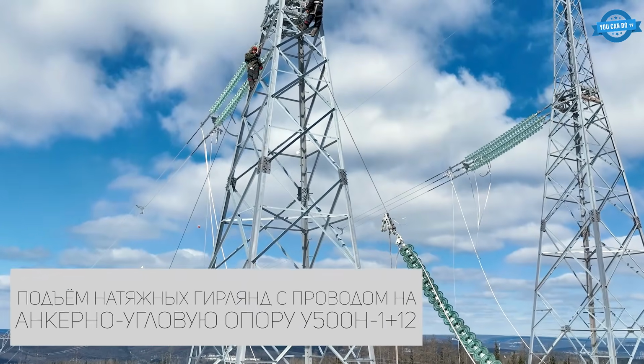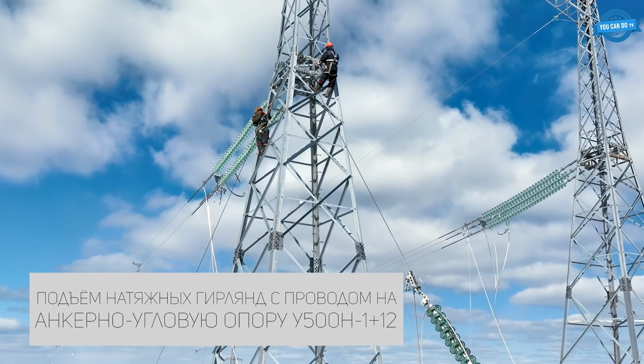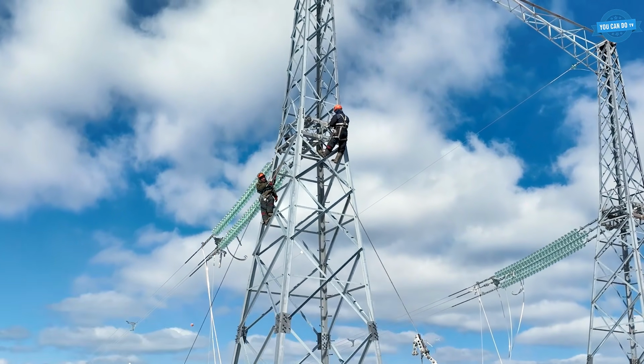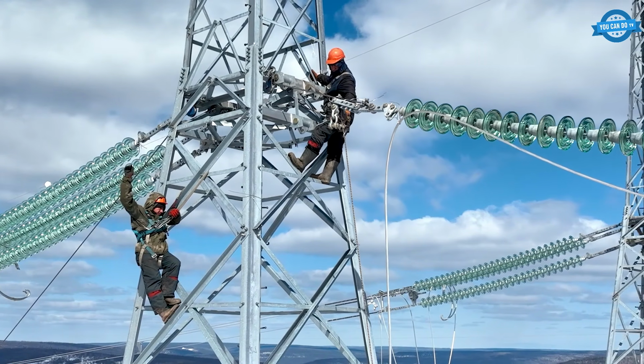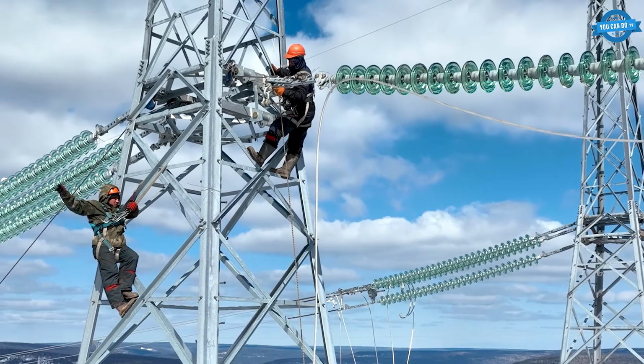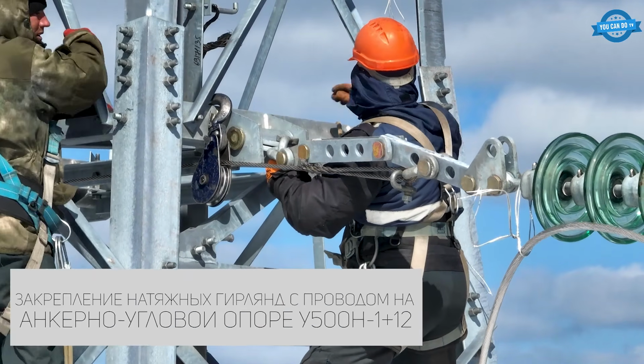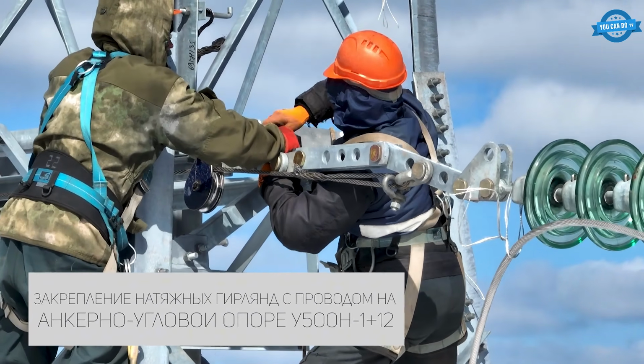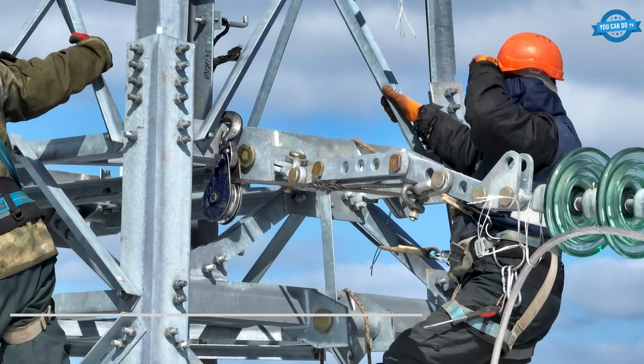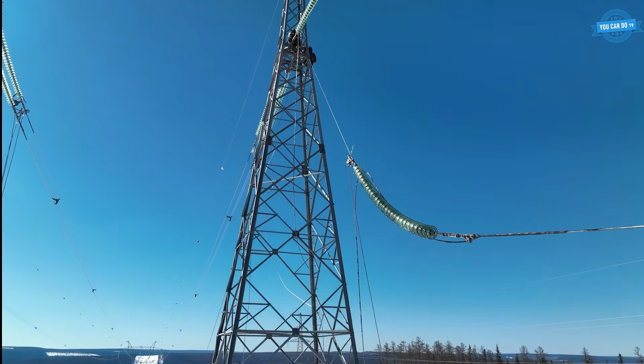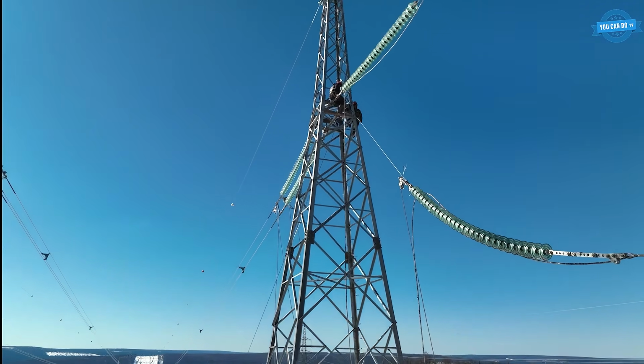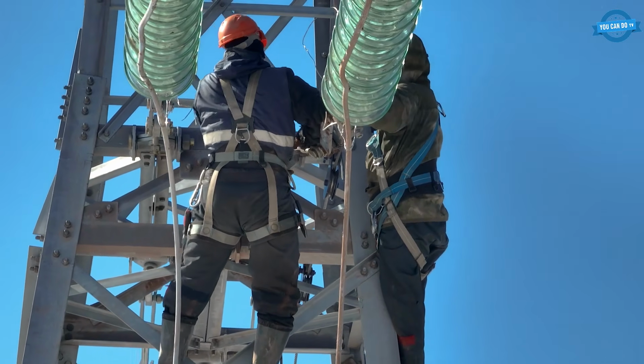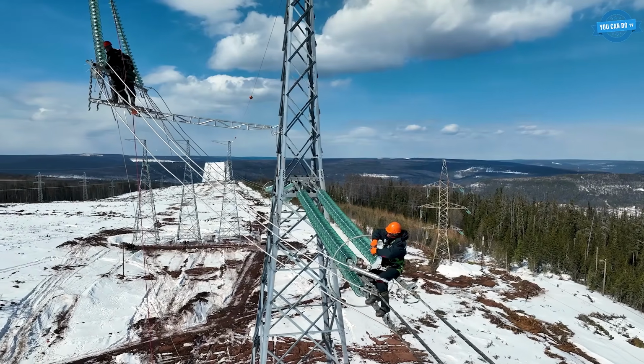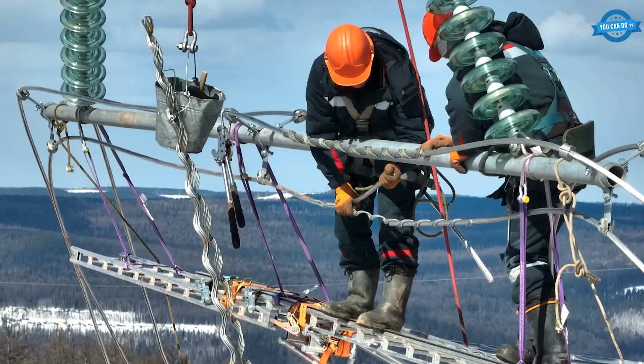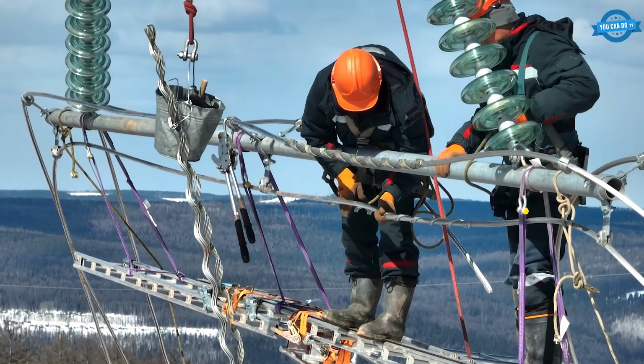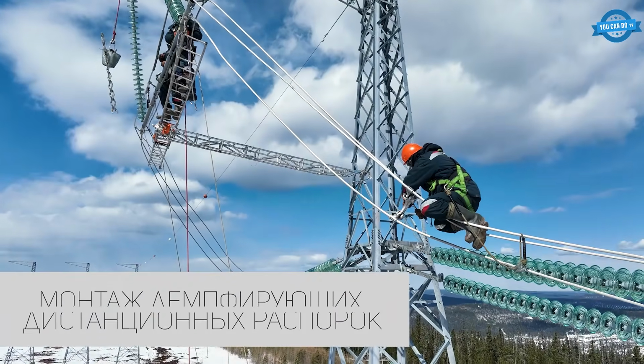Day 1 begins with de-energizing the 220 kilovolt line, installing anchors and portable earth grounding. Days 1 to 2 cover removal of existing conductors and the optical fiber communication cable on the section to be rebuilt. Days 2 to 4 see conductor and jumper installation in the new 500 kilovolt span. Tension insulator strings get assembled, lifted onto the anchor corner tower, fitted with damping spacers, bird protection devices, and signal marker balls along the conductors.